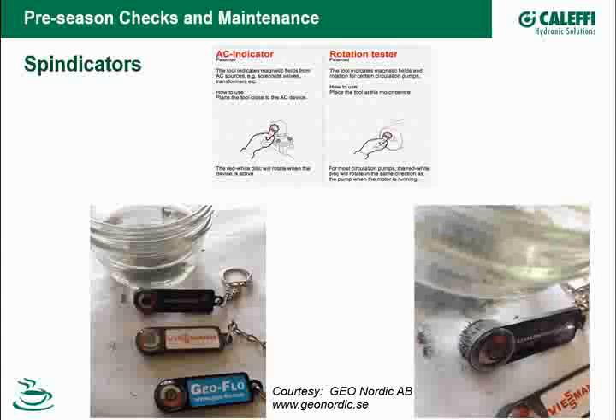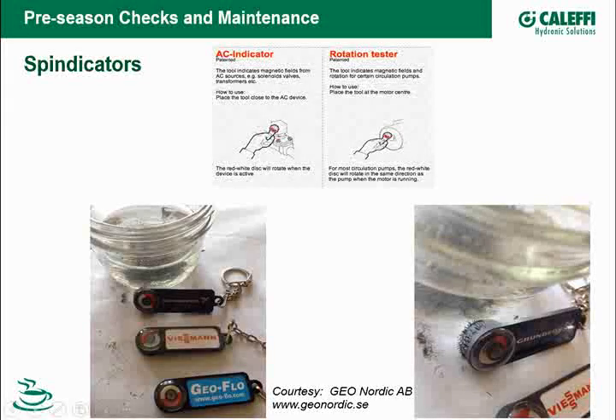It is handy for other things. You can put this on the end of a solenoid valve and see if that's been powered up. So you can see up there on the top, it shows you some of the applications. Now, it doesn't work on all the pumps. It doesn't work on the new ECM pumps that I've tried it on. And some of the brands out there, different brands of pumps, it doesn't work on at all. So even the old style permanent split capacitor motors.